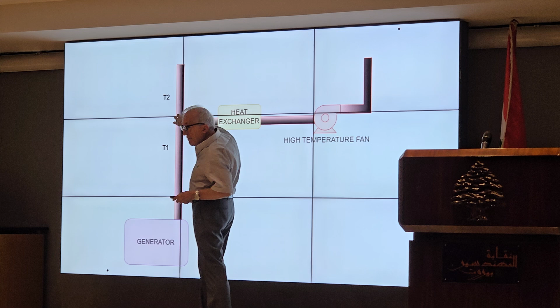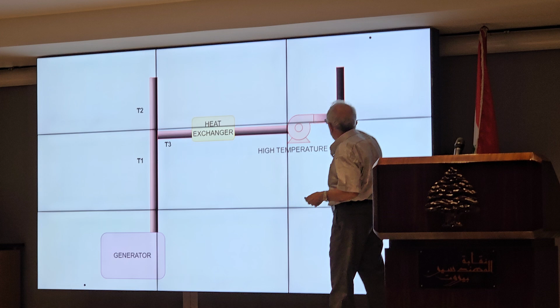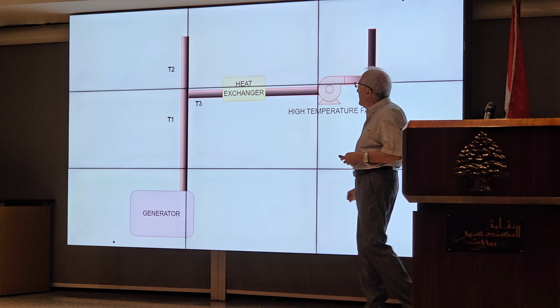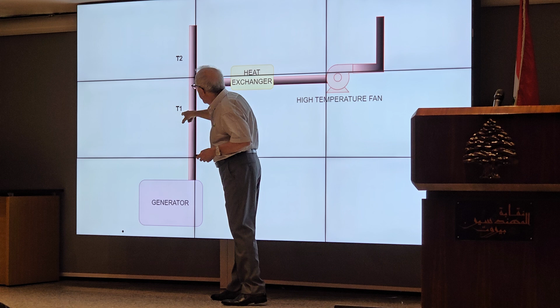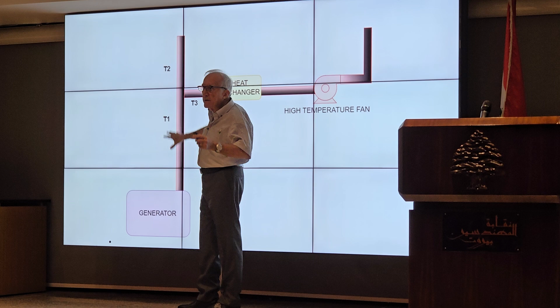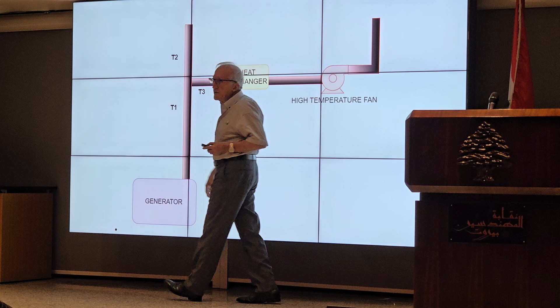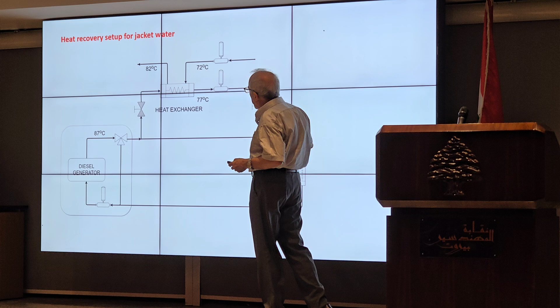Sometimes, instead of putting here the diverter, in one case, one client didn't want to have any pressure on the generators when our heat exchanger is working. So we did this setup for them. We put in a high temperature fan that sucks the heat through the heat exchanger, and we have 3 temperatures here. We try to keep this temperature a little bit lower than this one. That means that some of the air from outside goes in, and the generator will sense the normal pressure, the atmospheric pressure, because it is always open to the outside.